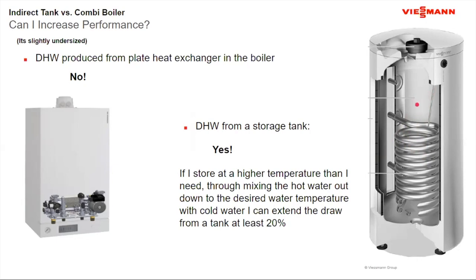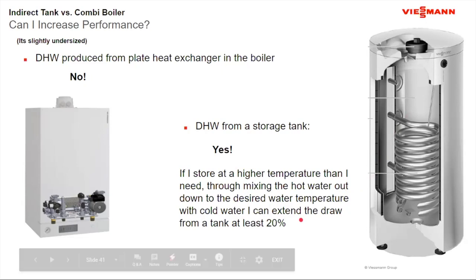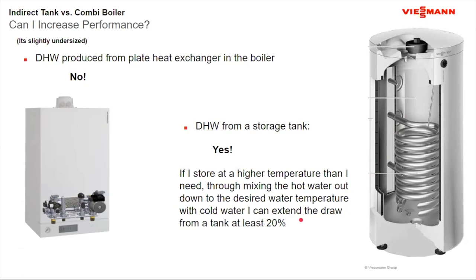But if I raise that tank temperature up to 145, I've increased the tank drawdown by about 20%. So the 35 gallons of drawdown is going to become closer to about 43 to 44 gallons. So I can extend it a little bit further by storing hot and then mixing down. Unfortunately, off the top of my head, I can't remember the formula, but when I put together the answers to the questions, I'll throw it in there. So again, another big advantage of what I can do with a storage type tank.